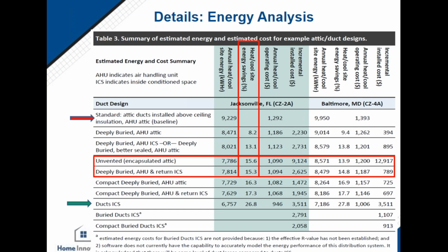As far as building a box around the air handler, those kinds of things are fine as long as they're fine with the code official. My experience has been that building boxes like that, or rooms, or even duct chases, can be very challenging to air seal. And they're not necessarily communicating with conditioned space either. So it's like a mini semi-conditioned attic, right? It's a semi-conditioned space.